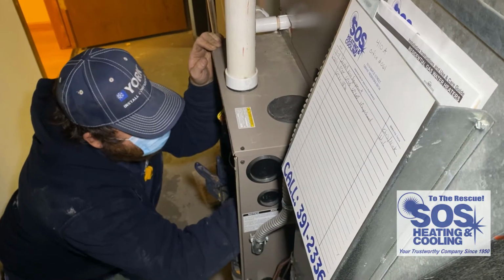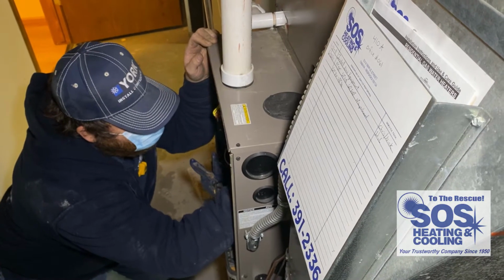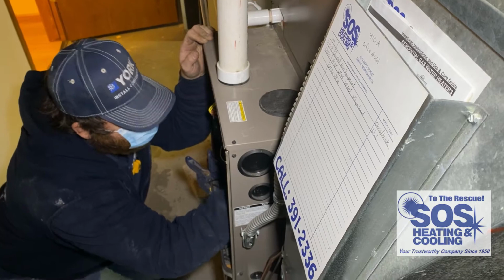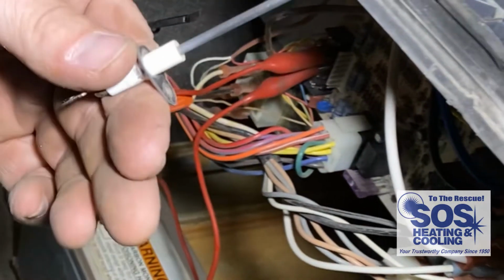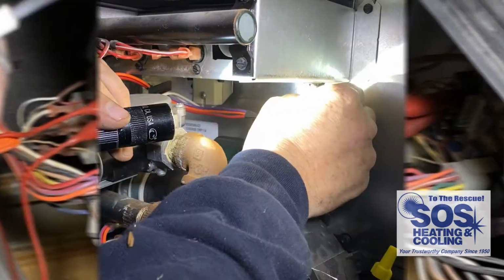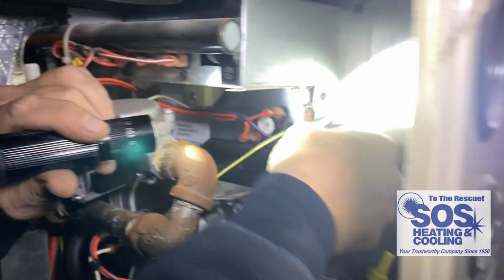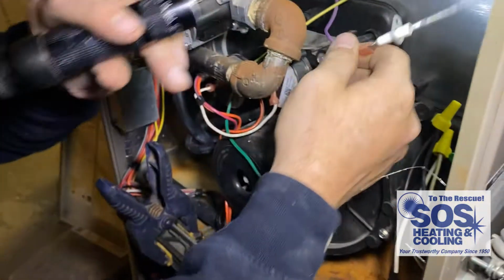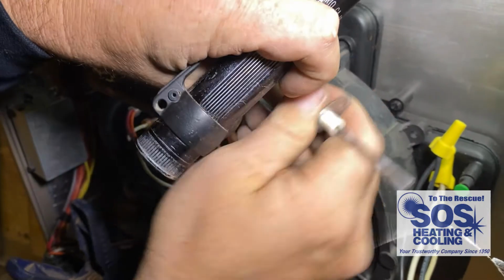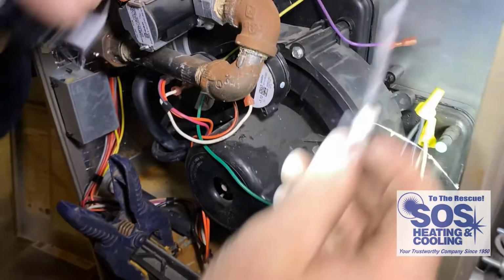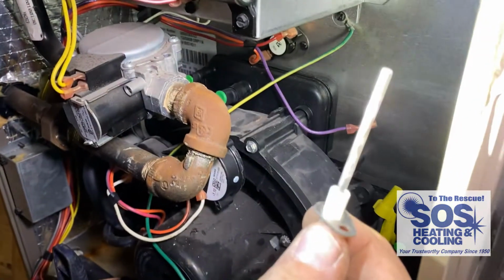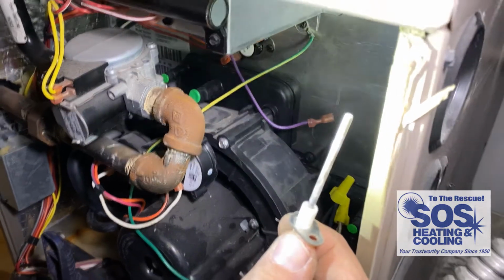And there's some other scenarios why a furnace may act up too. There's the flame sensor. I'll show you where that's at. Take that off of there. Now what you're doing is you're looking at this thing here. What happens, you get a film of dust and stuff on there. So you have to take this thing out and clean it up. I'll show you how to clean it up.